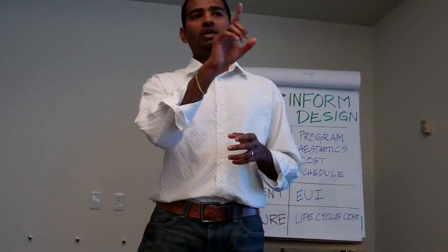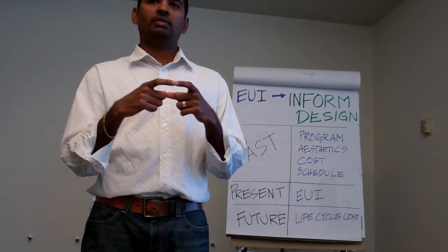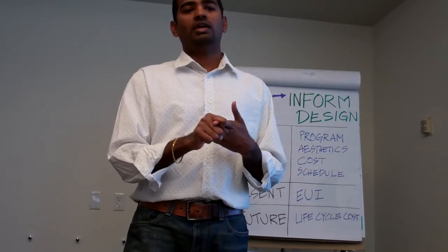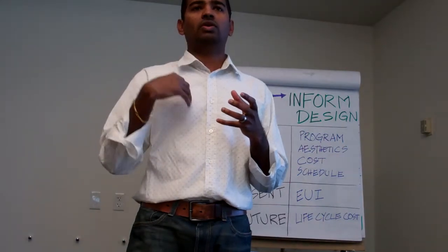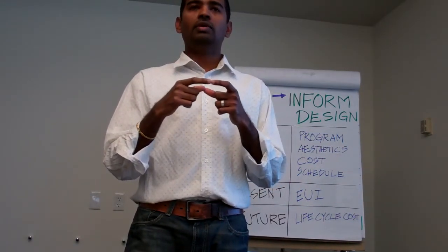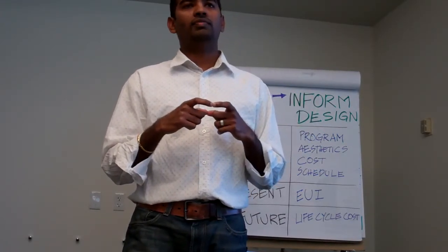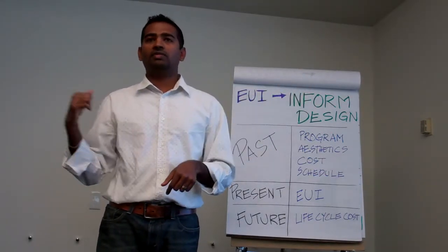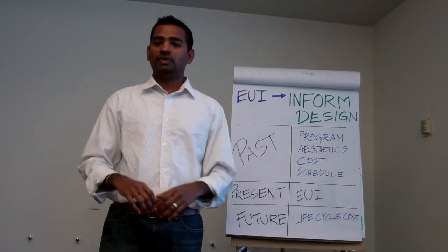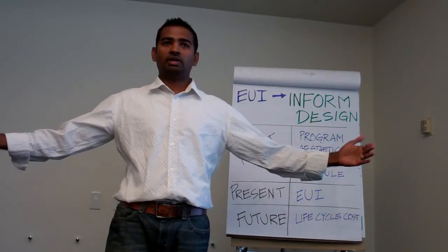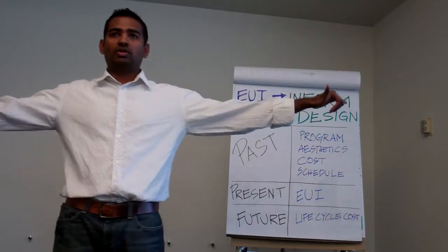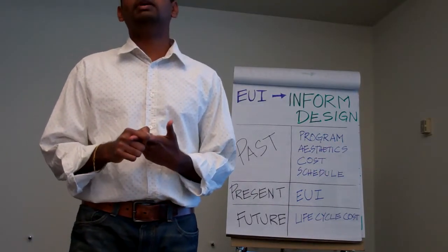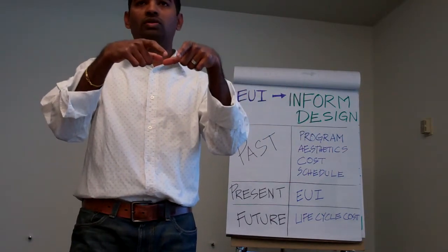Let me finish this thought on the zip code. Energy Star is a database of information collected from existing buildings through surveys. They normalize the data and try to equate it to our situation based on what you input. If you're in the middle of nowhere, let's say at Diné College, there aren't enough buildings around to give you a normalized average. If you put in a Phoenix zip code like 85016, there are enough buildings of the same type, say an office building, within 2 miles, 5 miles, whatever. If they can't find enough buildings within that zip code or mile radius, they go much farther, and after a limit it doesn't make any more sense. That's why we don't have data for prisons, because there aren't as many out there to normalize to our local zip code.